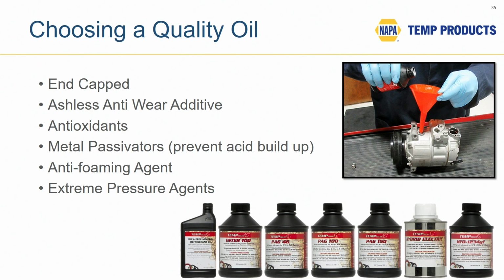They'll have anti-wear additives to prevent that little smoky particulate that you see building up in an older system. Antioxidants and metal passivators prevent acid and all kinds of corrosion buildup in the system. They also have anti-foaming agents. Think about it. If you walk out to a vehicle on a hot summer day and it hasn't been running for several hours, the static pressure in the system is probably, depending on the temperature, 70, 80, 90, even 100 PSI, just the static pressure throughout the system.